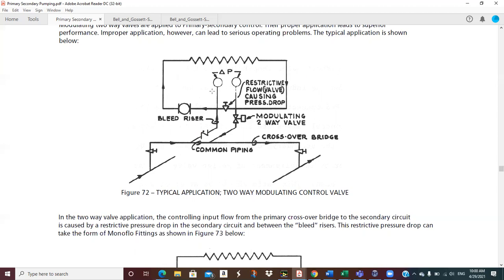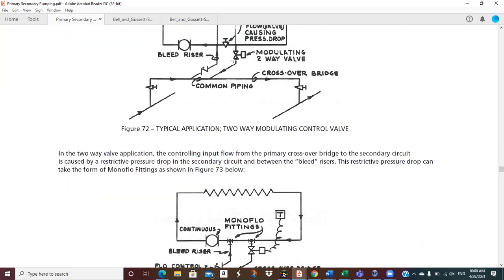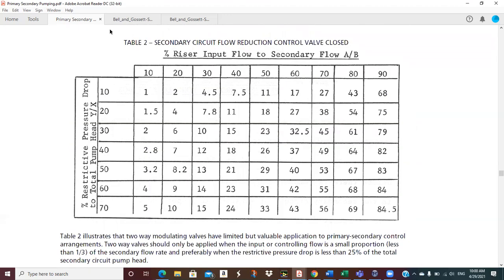Then, of course, the other thing is you have to look at what your delta P is across here divided by this total pump head. That's the other one. So that's the riser input flow to secondary flow in percent. And then on this y-axis over here, we've got the percent restrictive pressure drop to total pump head, and that's the secondary pump. Well, what you want, and this is the change in flow as you go from full open to full close, is for this to be 0.